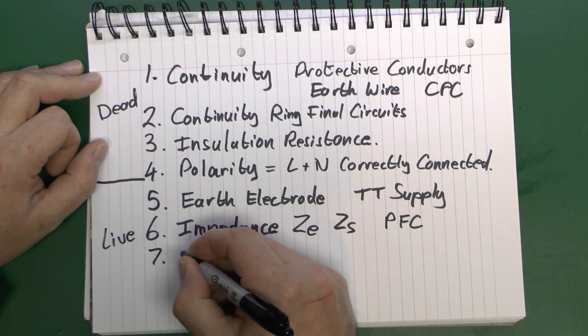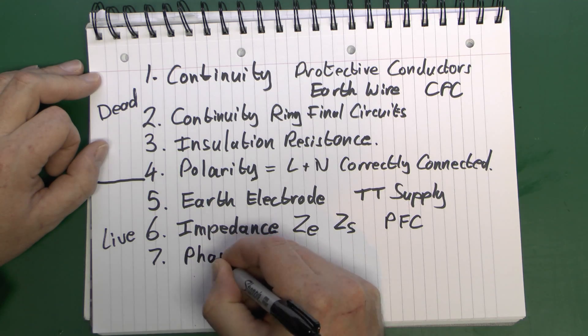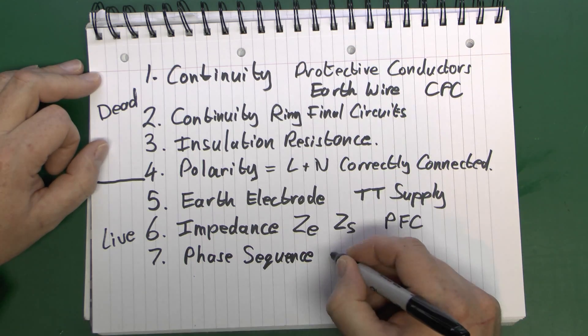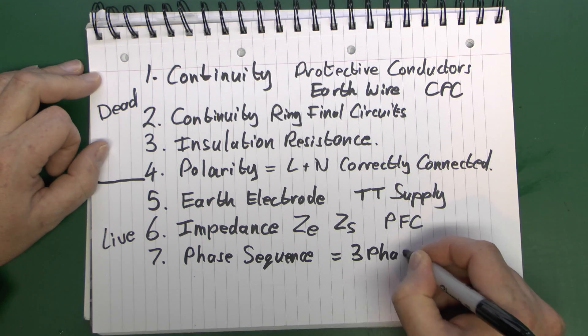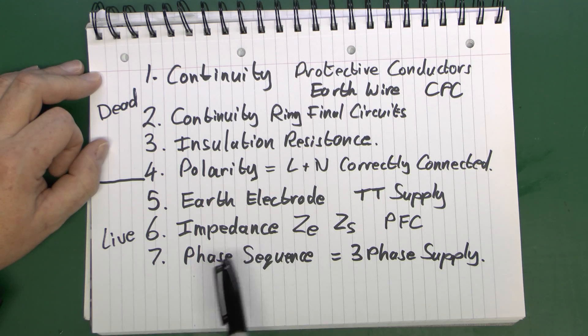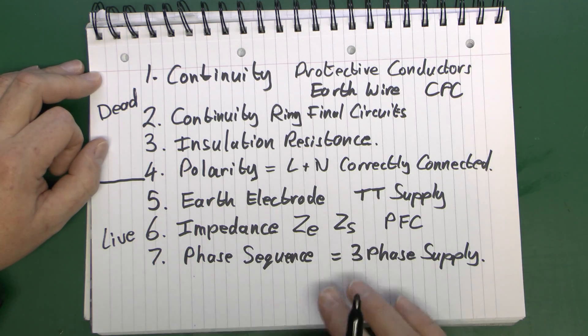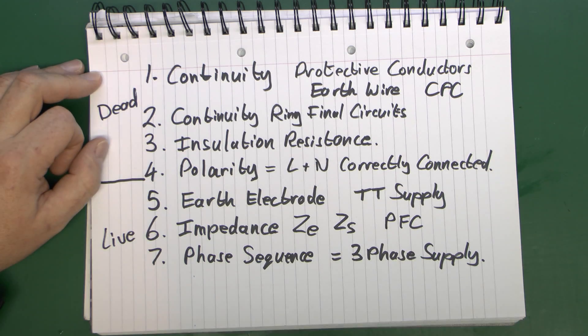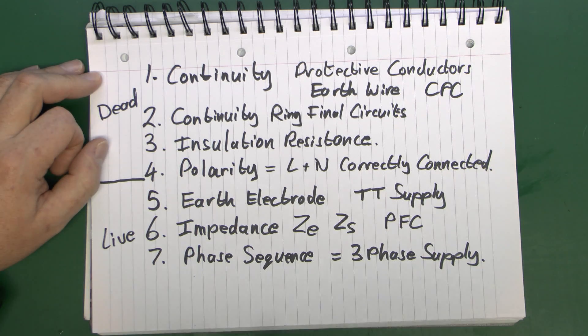Number seven is phase sequence. Rather obviously, this only applies if you have a three-phase supply, because if you've only got one phase, you can't really have a sequence. If you've got a three-phase supply, you need to make sure the phases actually go in the correct order. If not, and you've got three-phase motors attached, they'll turn backwards — which generally causes expensive and probably irreversible damage to the equipment. So only applicable for three-phase supplies, but if you've got one, it's certainly necessary.